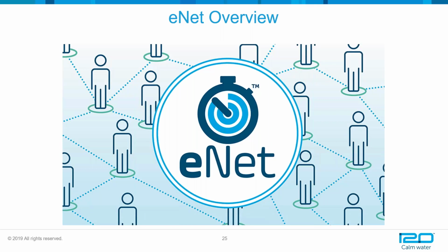I tried to use this alarm about the nightline, but I have a few comments about that. First of all, it's almost invisible when you get the alarm screen, so it's very, very low lines, and you cannot define it. Once we are working with the DMA and we know how many customers are served, it's easier to calculate the expected nightline. So it would be very helpful if you can add this line, this graph, of the expected nightline. And once you have a problem, you can see that. And then to get this line in the monitoring screen, not in the alarm screen.